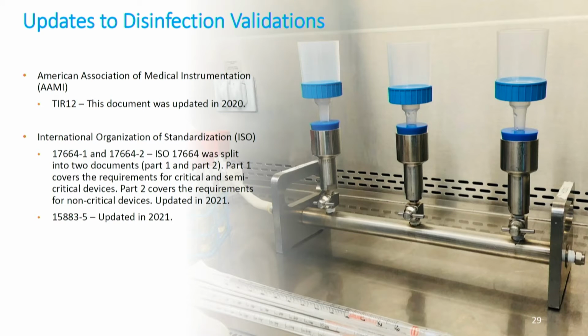Now I'm going to go into disinfection validations. AAMI TIR12, which is a technical information report, got published in 2020. In there, there's extensive information, a section on disinfection. We don't have a lot on disinfection for reuse, so we added that into this section. And I'm taking it further and going to write a standard on it, just to make sure that manufacturers have an idea of how to select what the categories are going to be for disinfection. But ISO 17664-2 also got published, and that is for non-critical devices. So if you have non-critical devices, this is the ISO standard that you want to look at as well.